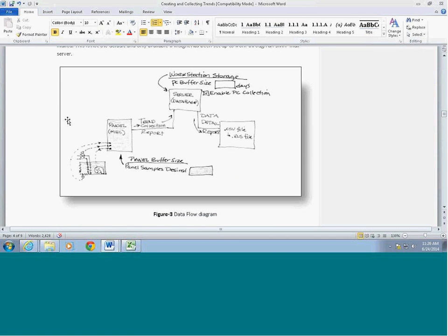Okay. So in the very first session, we talked about network structure. We did already talk a little bit about this, but I wanted to reemphasize this for Siemens. I have three steps for setting up a trend. One is you need the primary control panel. You need to have the trend set up there. This is what actually saves the memory, saves the value for these points. And you have limited memory here, so you only want to store a couple days tops.